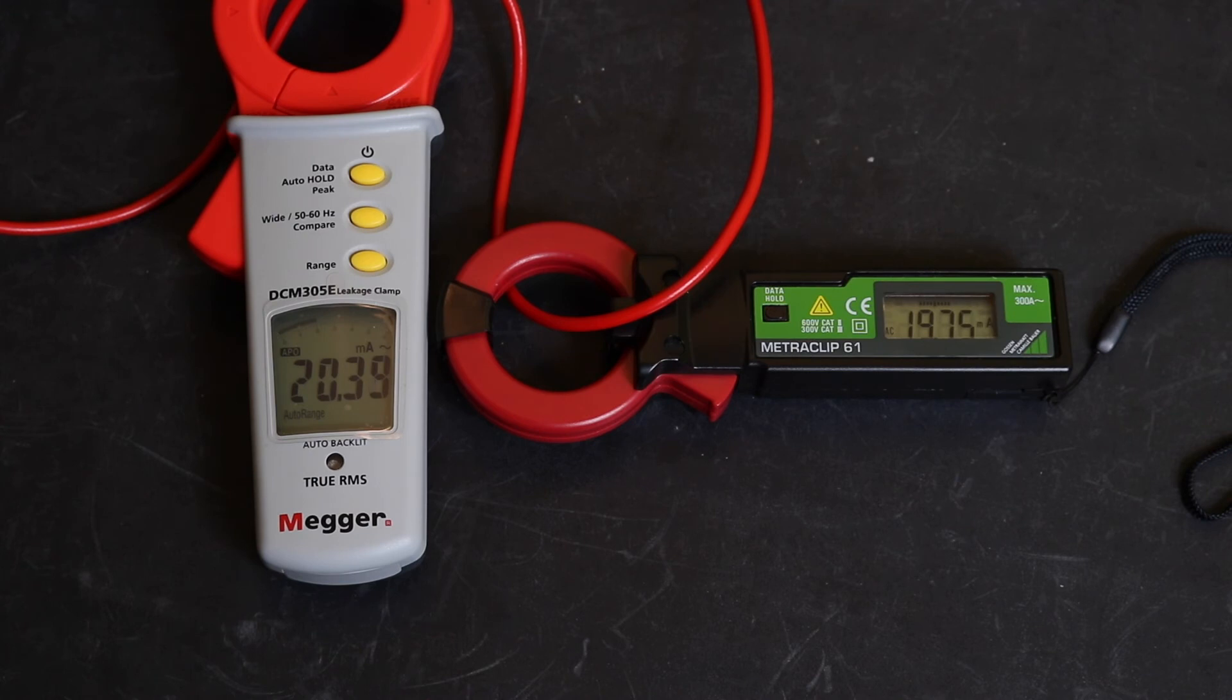Okay, so we're now looking at 20 milliamps going in. Go to 15 milliamps going in. We're looking at 15.29 and 14.82. And then we'll drop down to 10 milliamps. And then we'll go down to 5 milliamps. There's a problem with injection test sets. They're really designed for really low stuff like this. So we're looking at 5.049 and we're looking at 4.89.